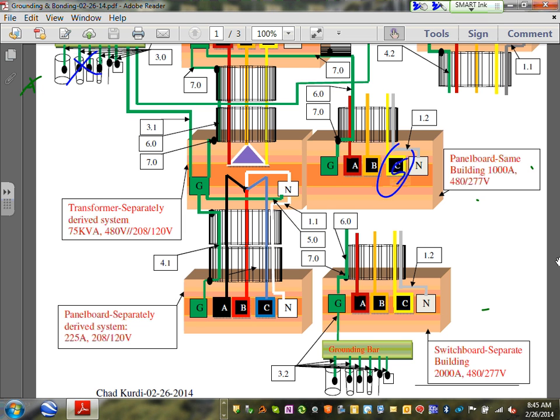The first thing you need to do when you have a transformer, basically, is what we call number 5: bond the neutral to the ground. You have to size the new neutral. Then you have to bond the conduit, bond the transformer enclosure. Can you guys see that? Number 4, supply side bonding jumper, bond the transformer enclosure to the panel. So 1, 2, 3, we also need to bring an equipment grounding conductor and a load side bonding jumper. These are the 5 things. I'm going to get rid of this one here so it doesn't confuse us. Okay, so I need 1, 2, 3, 4, 5, okay, 6 right here. 6 things I need to size for the separately derived system.